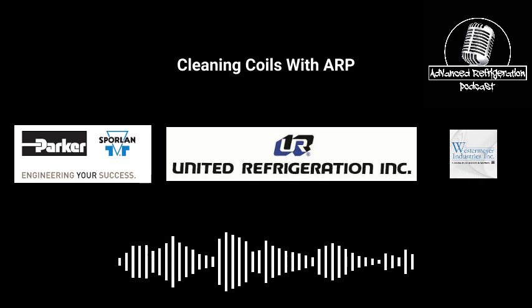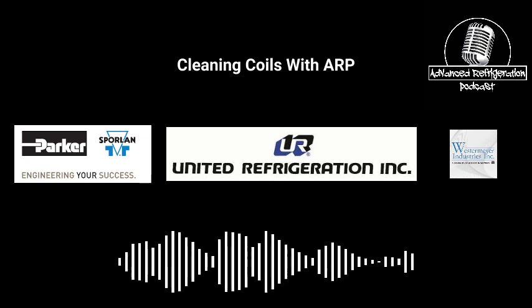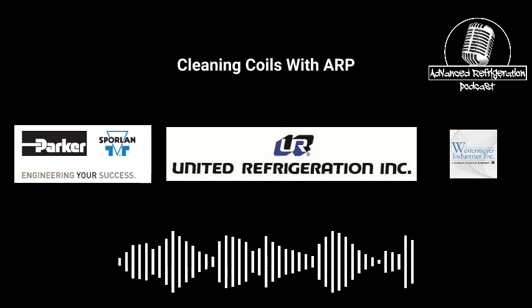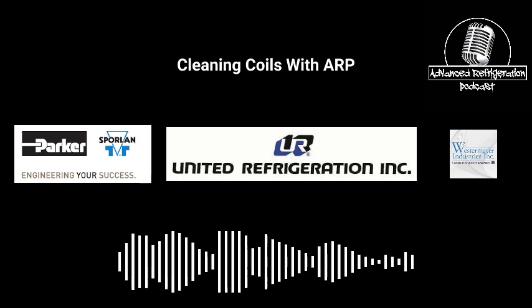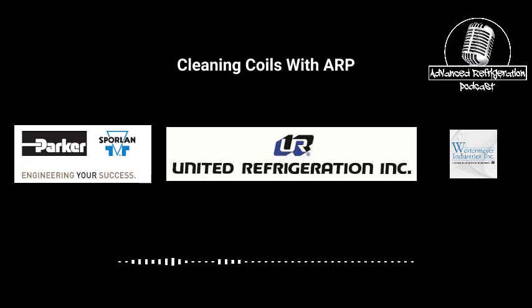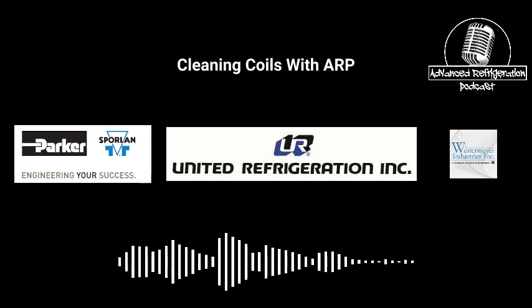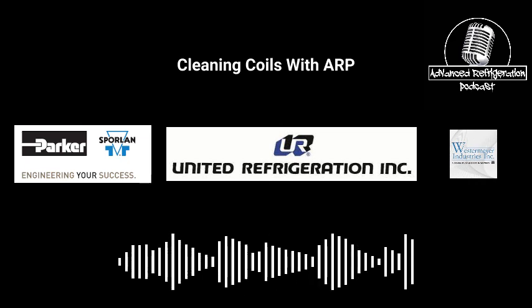Now, what you're going to want to do is get this coil wet. A lot of guys, I've seen them leave the condenser running and shut down one fan at a time. I'm not a big fan of that. I will take the condenser apart, start loosening up all the fan guards, then I'll shut everything down, and then move from there and do the condenser. I can only have so much downtime on this condenser before they start freaking out. It should take roughly about an hour and a half to properly wash a big coil.